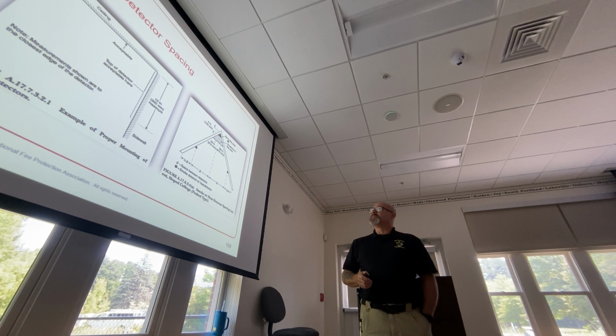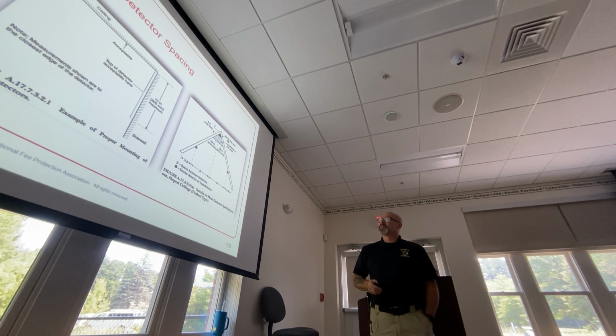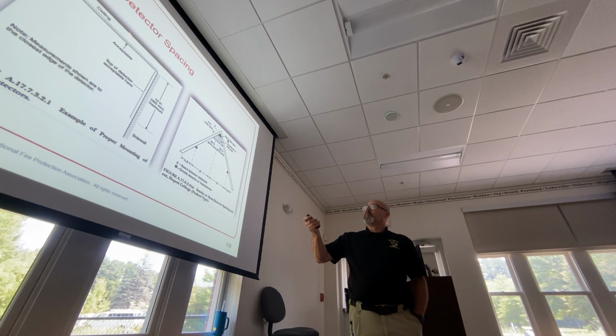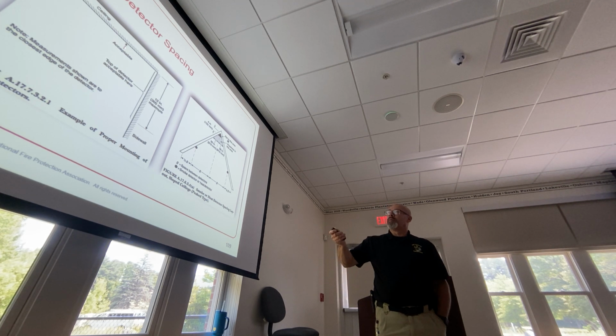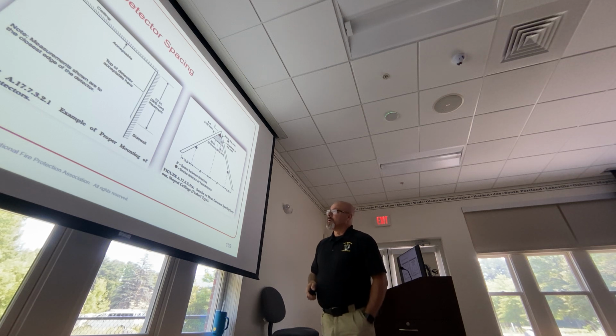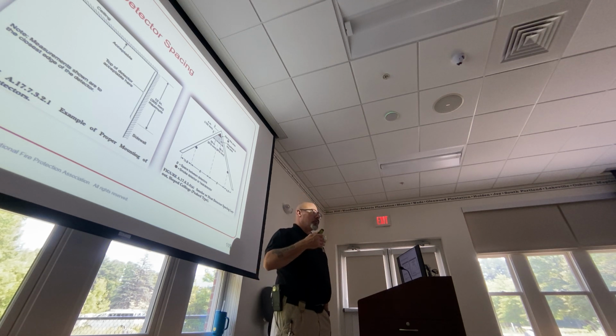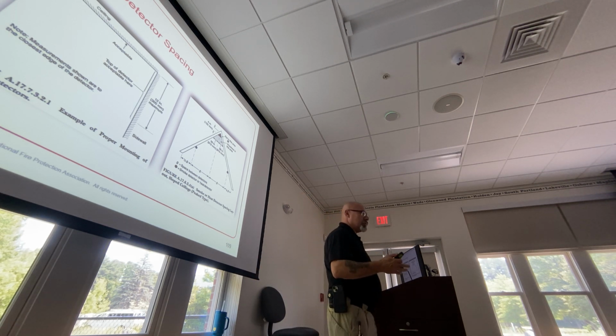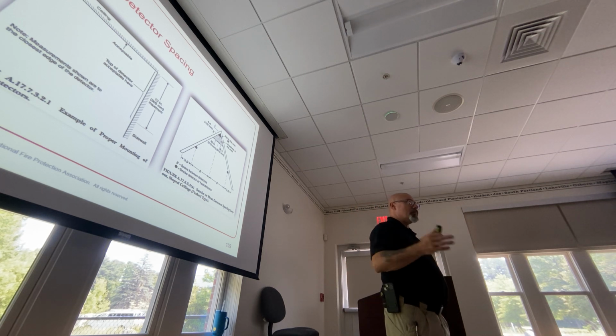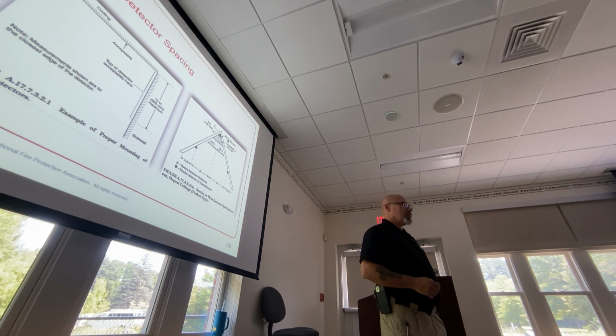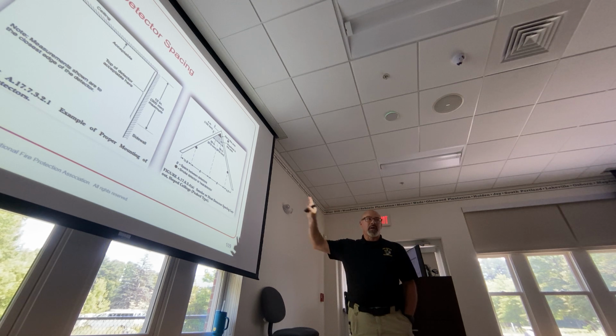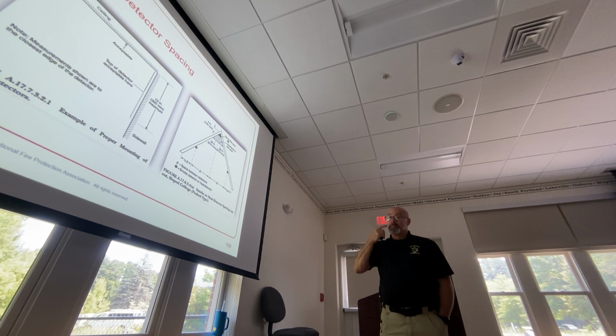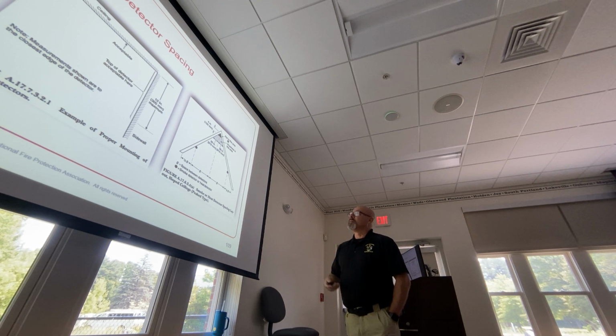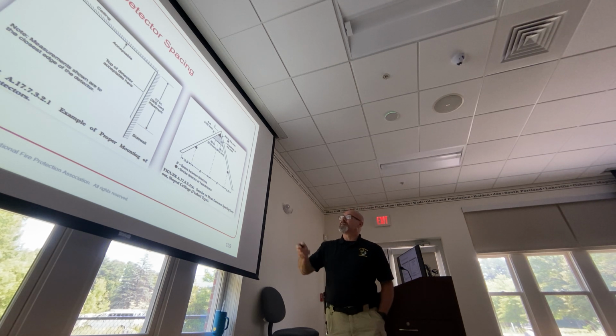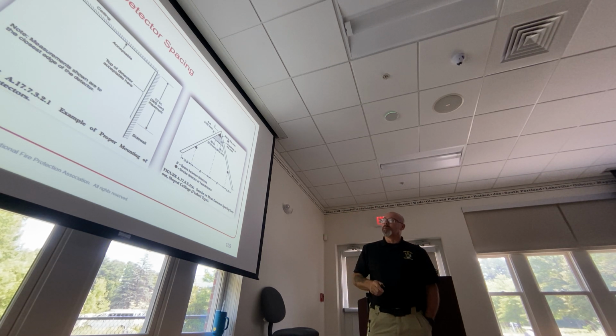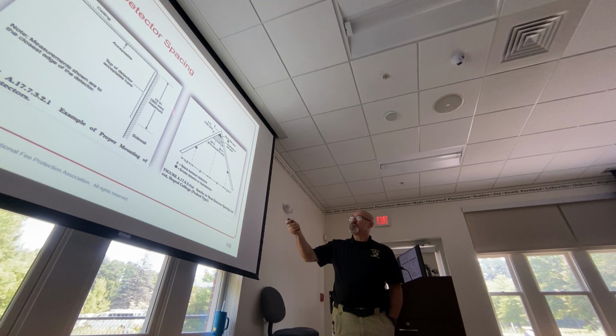This one here, you'll see something like this on the test. Acceptable areas of where the detector can be mounted. And keep in mind, the manufacturer will tell you, they'll give you the mounting information. If it's a legitimate company, it's going to meet 100% of this. If there's no information on it, we understand that the ceiling is acceptable. We'll see a slightly different variation of this in a second.